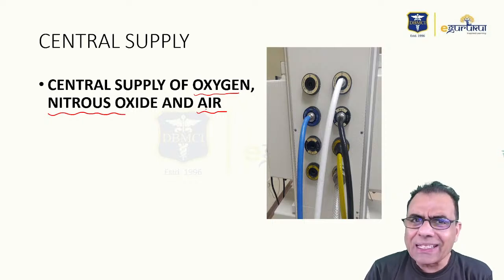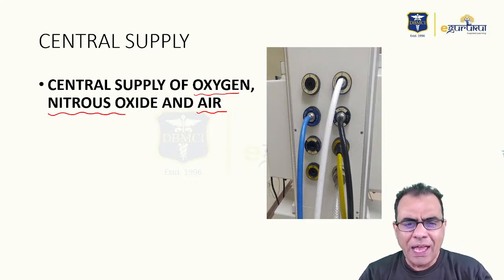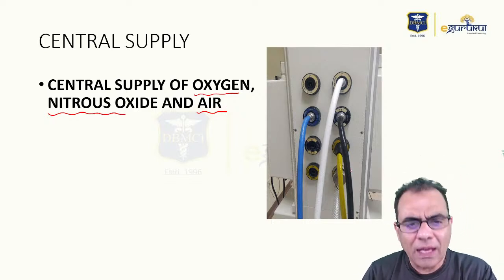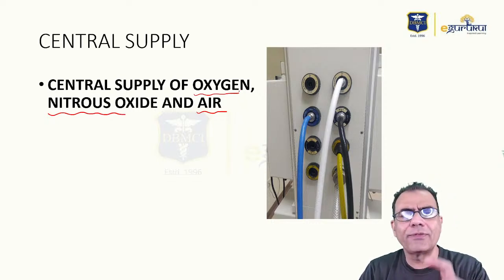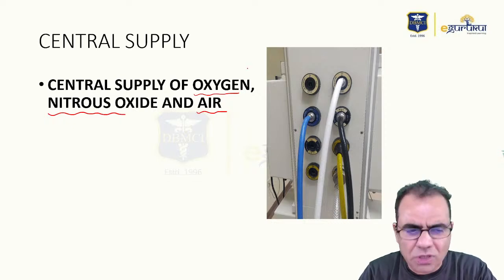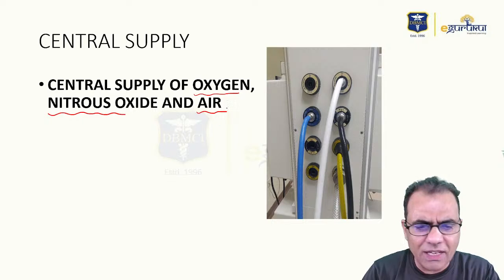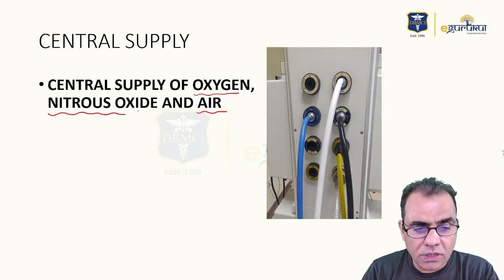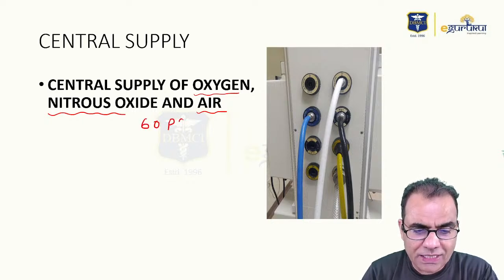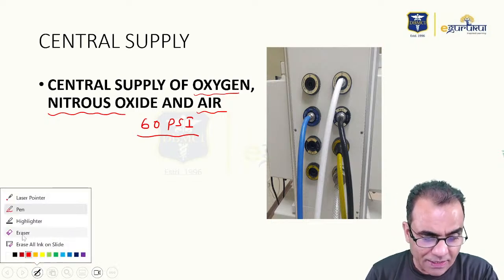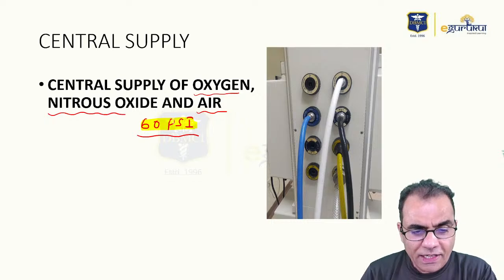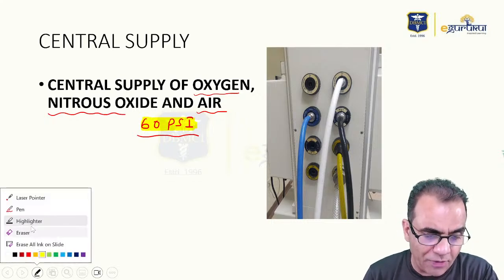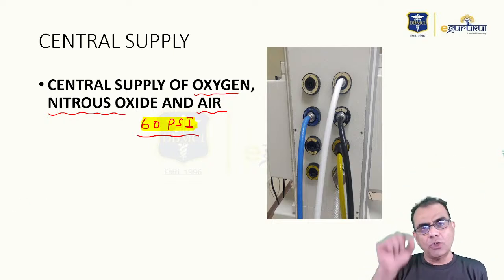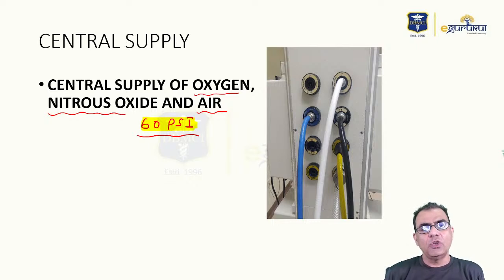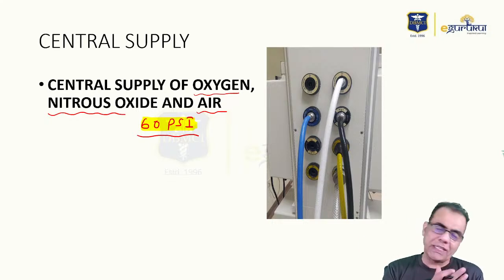That is why I was telling you that for the air cylinder, if you want to skip it, that is also fine, because air is almost always supplied through central supply. Even all modern machines don't have any provision for attachment of an air cylinder at the anesthesia machine. So mostly it is oxygen and nitrous oxide cylinders. Anyways, through central supply, oxygen, nitrous oxide, and air are supplied at a pressure of 60 pounds per square inch. 60 psi. In your books, you will find the answer given as either 50 psi or 55 psi, depending on which book they have picked, because in the US it is supplied at 50 psi, and in the UK at 55. So you need not remember the UK and US. In India, the central supply is at a pressure of 60 psi.